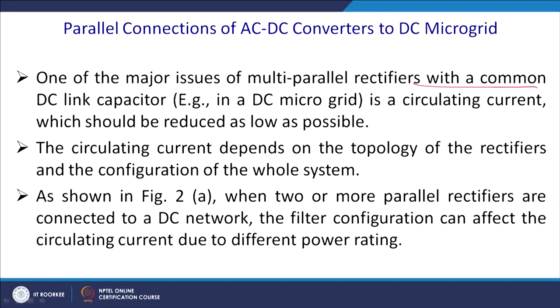One major issue in multi-parallel rectifiers with a common DC link capacitor, as in a microgrid, is circulating current. If there is a slight mismatch between the pole voltages of the two DC buses, a circulating current can exist between them. This circulating current causes heating and thus power losses. The circulating current depends on the topology of the rectifier and the configuration of the overall system.